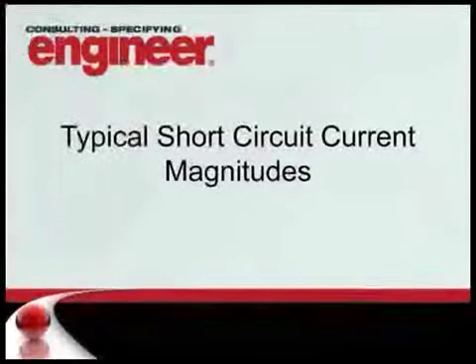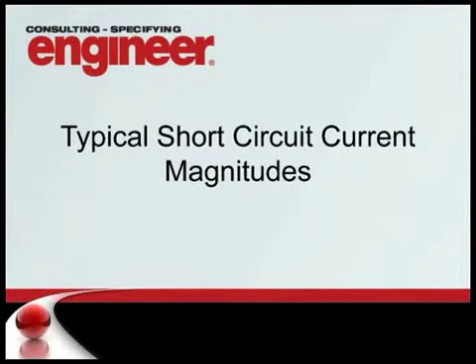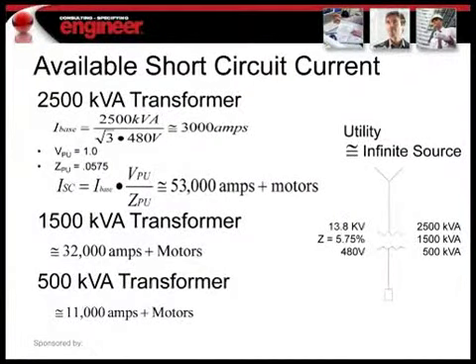So when you're specifying transfer switches, you need to identify all of these parameters either in your specs or on the single line diagram. I'd like to demonstrate some calculations that relate to fairly common system sizes that might serve healthcare facilities. This diagram shows a single utility source serving a transformer that might be a 2500 kVA, a 1500 kVA, or a 500 kVA transformer, fairly typical for a small to medium-sized hospital or clinic characterized as an institutional occupancy. Based on some very simple calculations, you can see the fault current magnitudes range from between 11,000 amps and up to 53,000 amps, plus the contributions from the motors within the facility. This just gives you an idea of the magnitude of the short circuit currents available in an arrangement like this.